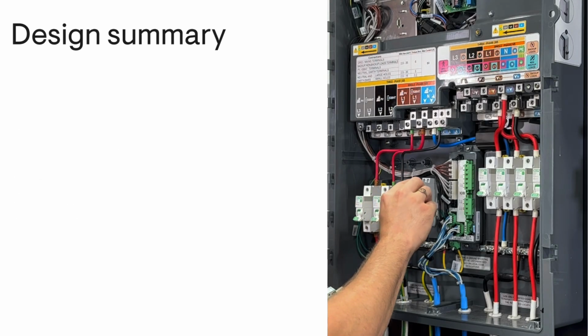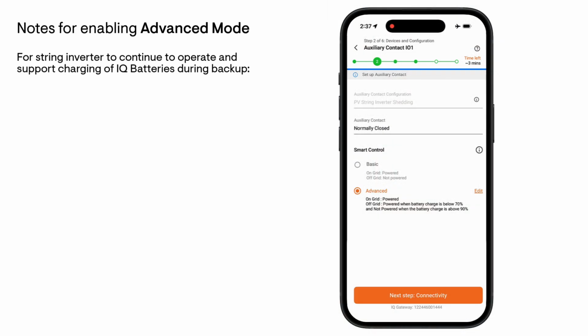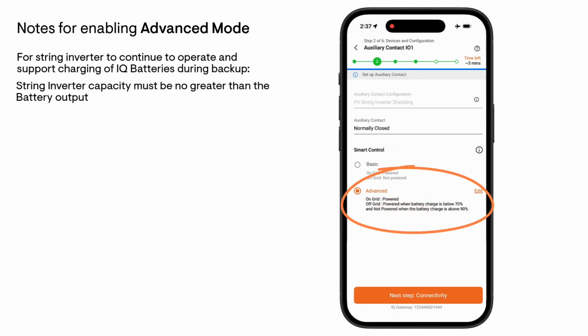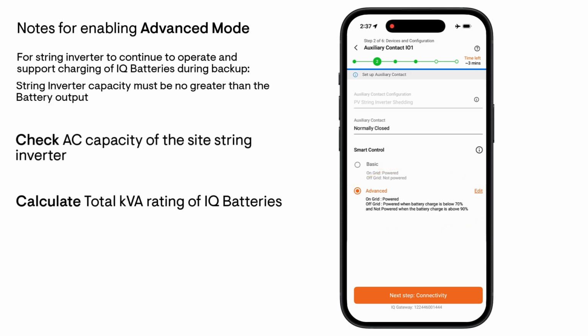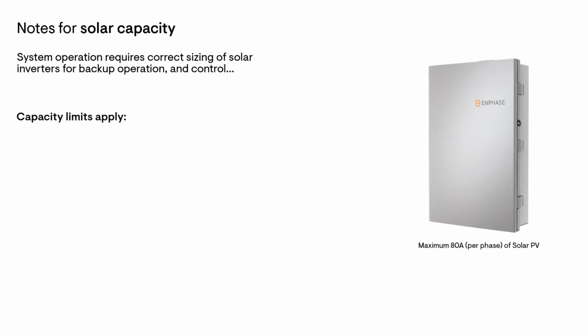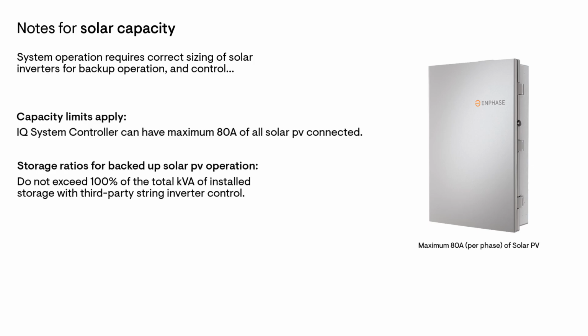Design summary. For a string inverter to operate during backup events, its AC output must not exceed 100% of the combined AC output capacity of all the installed IQ batteries. Always remember to verify the AC capacity of the string inverter, calculate the total kVA rating of all IQ batteries that are installed, ensure correct inverter to battery sizing for backup operation, and confirm compliance with DER capacity limits within the IQ system controller. The IQ system controller supports a maximum of 80 amps of total connected solar PV generation. For third-party string inverter backup operation, do not exceed 100% of the total installed battery kVA capacity.